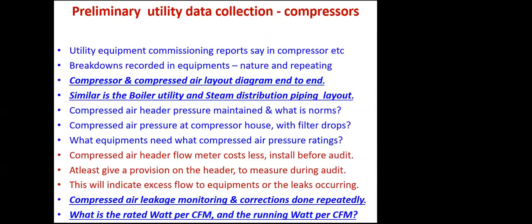Especially the preliminary data on the compressors. Everyone, we have all purchased the compressors, but we also have to ask the compressor OEM to do the commissioning report, like the pump up capacity. Or if it is possible, let us say the energy authority is coming to the industry, after a week or a month, 2 weeks, try to have your insertion type mass flow meters, thermal mass flow meters available.